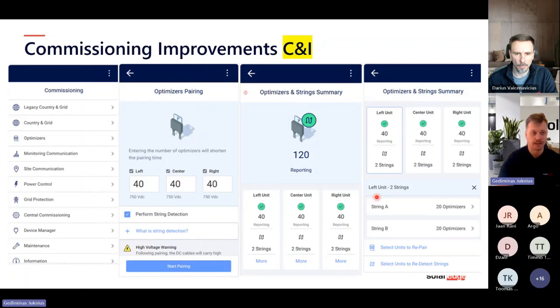So now, instead of pairing, there is a choice of optimizers, and you can set how many optimizers are connected per unit. This is, for example, from the Synergy inverter with the 3 units. So let's say a 90 kilowatt inverter, so 30, 30, 30. A new thing we do, we can also find the strings. So we know the strings, we detect the optimizers, and we can tell how many optimizers we detected in a specific string. So it's easier for you to detect a problem, easier to do the maintenance, and much easier to do the mapping.